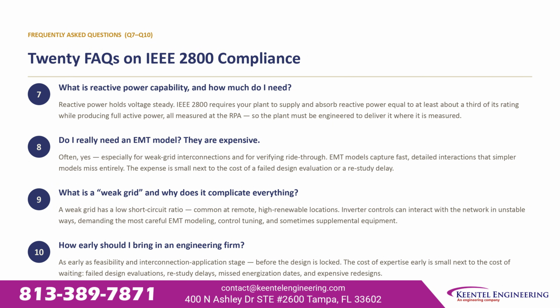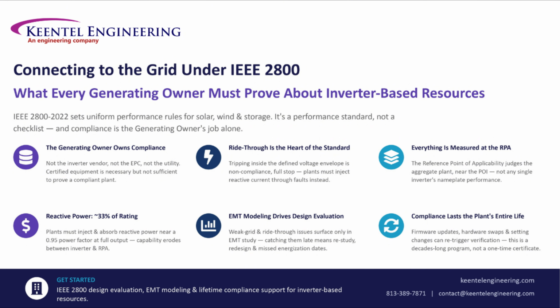What is a weak grid, and why does it complicate everything? A weak grid has a low short-circuit ratio, common at remote, high-renewable locations. Inverter controls can interact with the network in unstable ways, demanding the most careful EMT modeling, control tuning, and sometimes supplemental equipment. How early should you bring in an engineering firm? As early as the feasibility and interconnection application stage, before the design is locked. The cost of expertise early is small next to the cost of waiting, failed design evaluations, restudy delays, missed energization dates, and expensive redesigns.